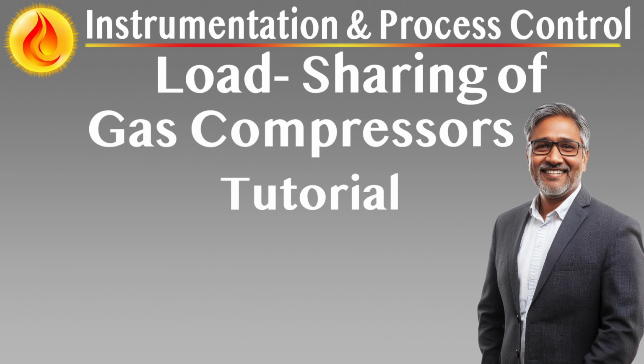Pressure override control, POC. Dual algorithm control: PI correction for exceeding pressure flow thresholds, and predictive control to dampen rapid deviation rates. The POC output always favors surge protection logic and only augments recycle flow when needed. It prevents sharp pressure spikes or suction dips that could destabilize the compressor train.